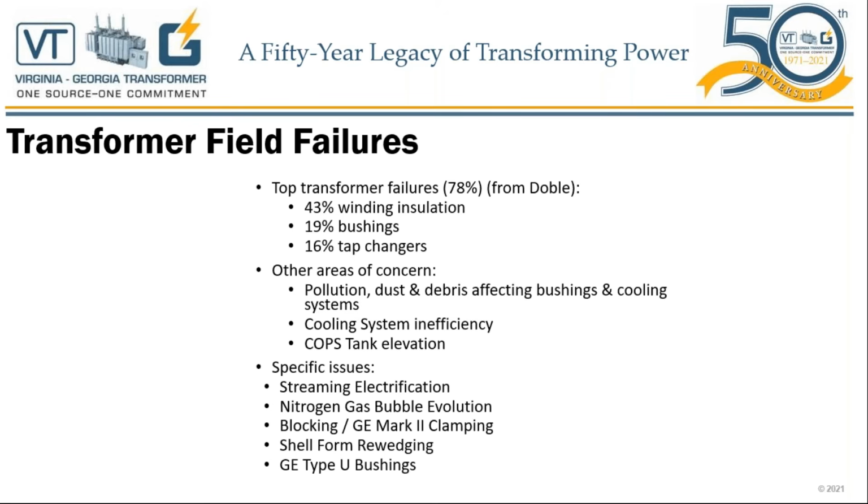This is why we are doing this webinar, to connect those three stress points together and allow our end users to have a great understanding of what makes a transformer fail or run perfectly fine in the field for years to come. Other areas of concern are pollution, dust, and debris affecting the bushings and cooling. So where you install this transformer will affect the life of the transformer as well.